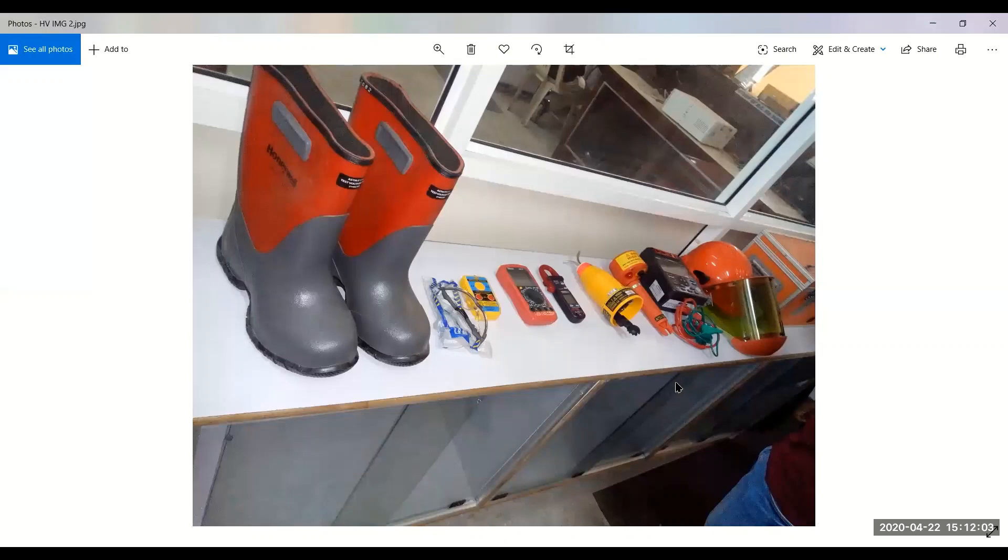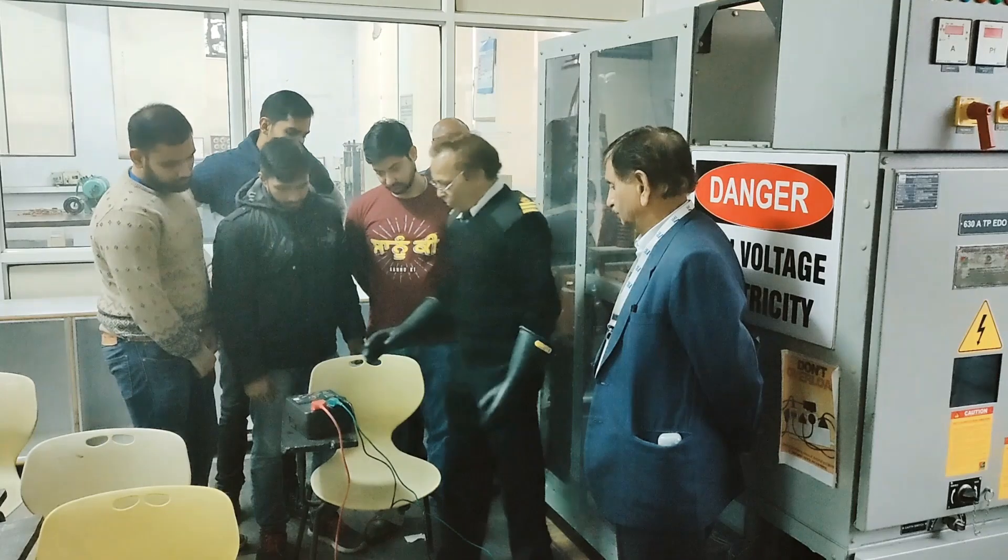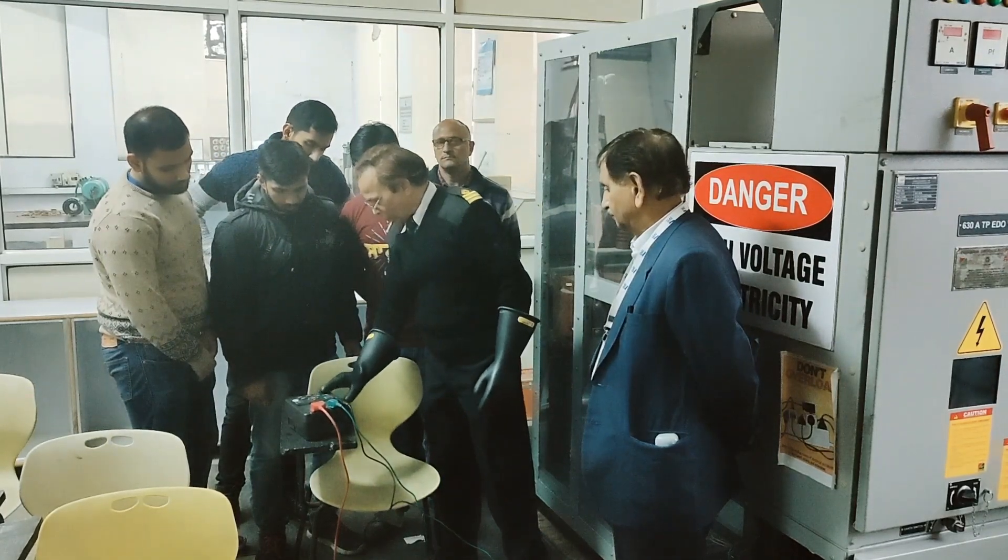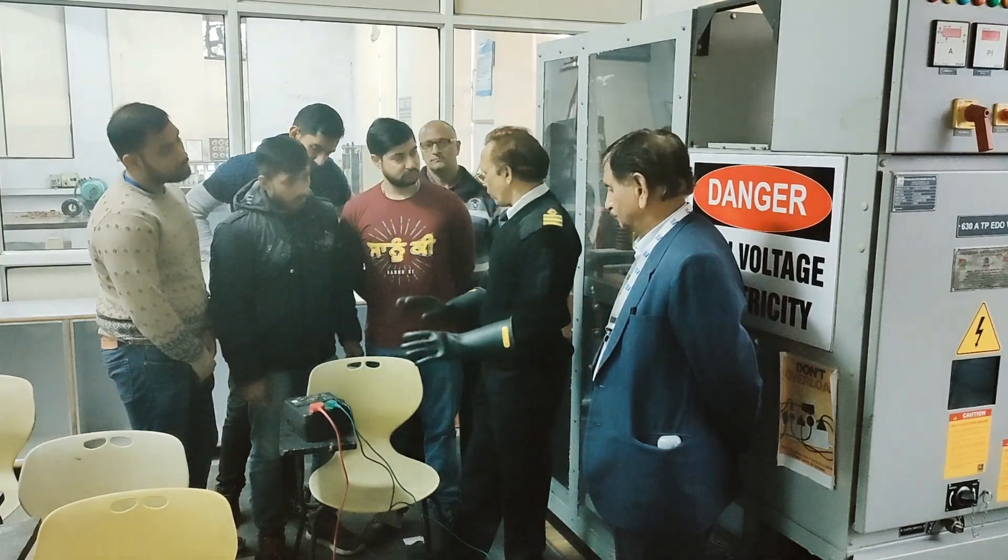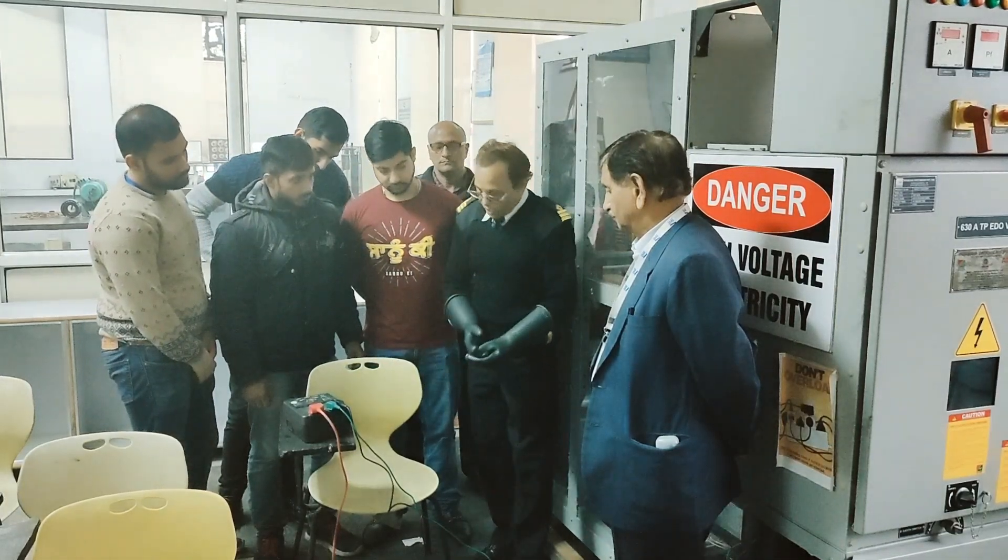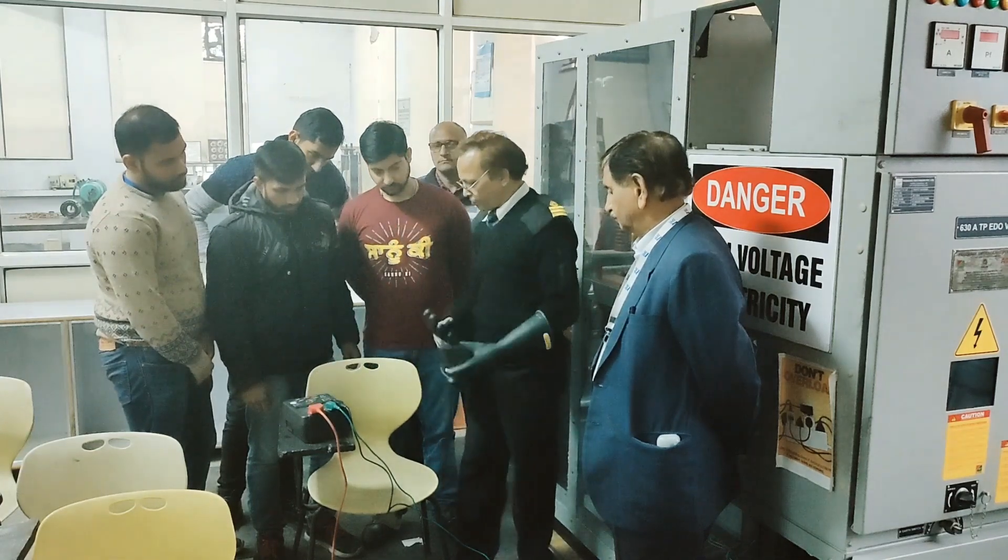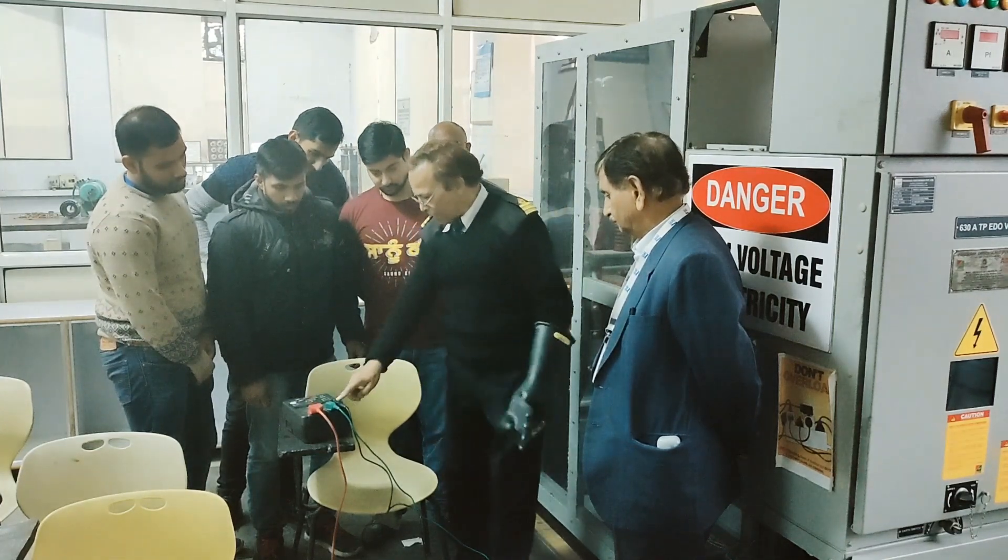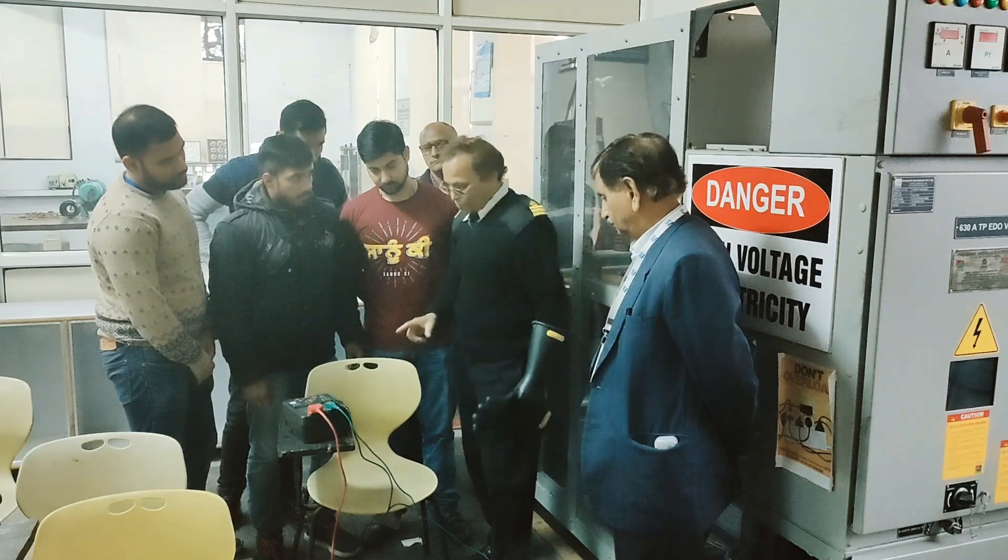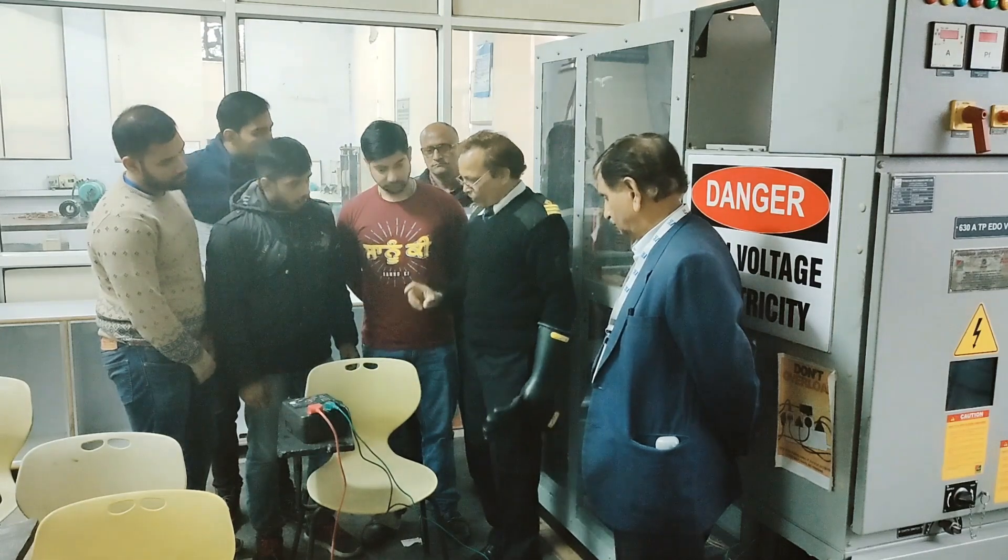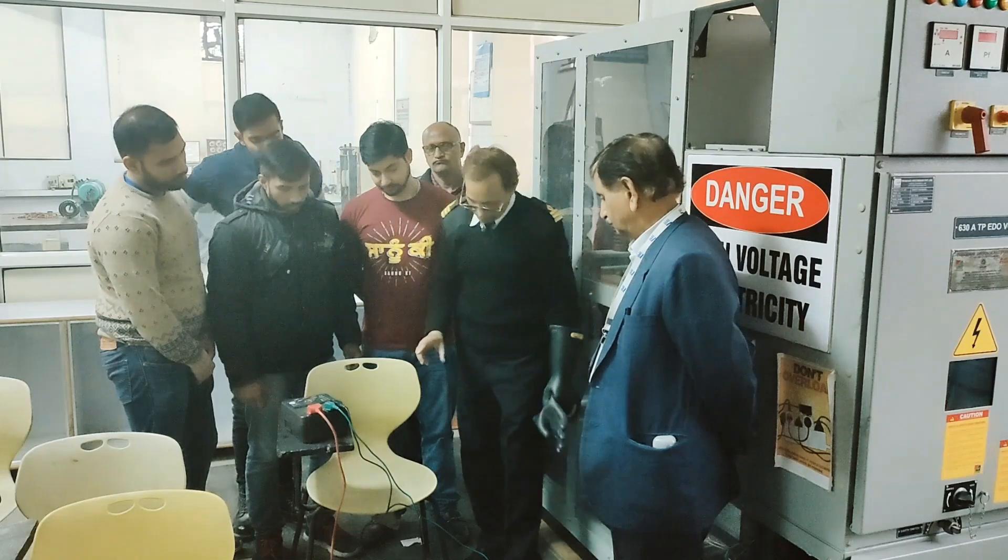Now we will continue with this. I will teach you how to check the insulation of the high voltage equipment. We can take it up to more than 5,000 V. But we will test it on the 5,000 V. Before, now I have three terminals. One is the line terminal, this is the earth terminal and this is the guard terminal. Guard terminal is for safety of equipment and safety of personnel.